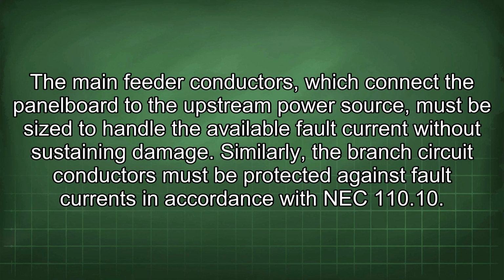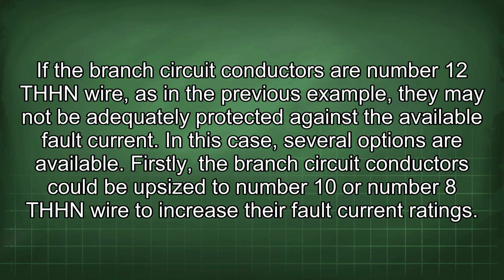The main feeder conductors, which connect the panel board to the upstream power source, must be sized to handle the available fault current without sustaining damage. Similarly, the branch circuit conductors must be protected against fault currents in accordance with NEC 110.10. If the branch circuit conductors are number 12 THHN wire, as in the previous example, they may not be adequately protected against the available fault current.